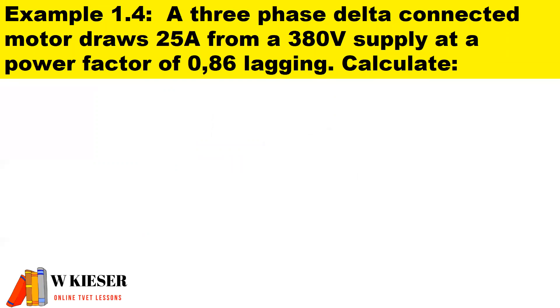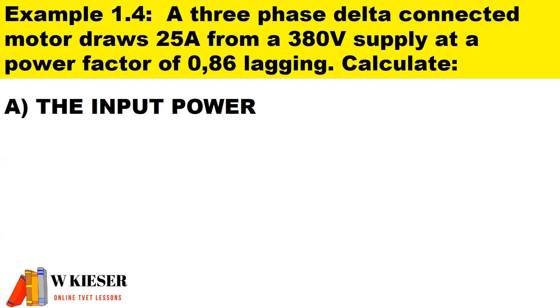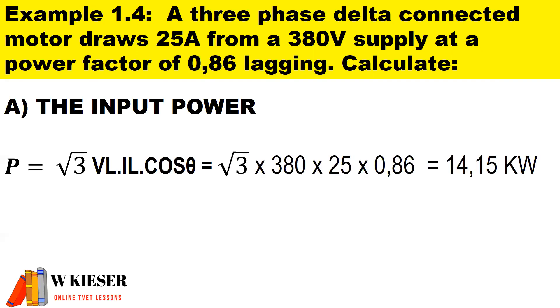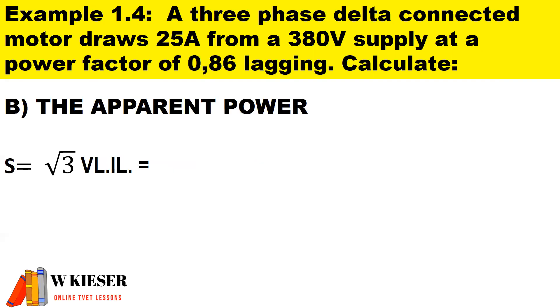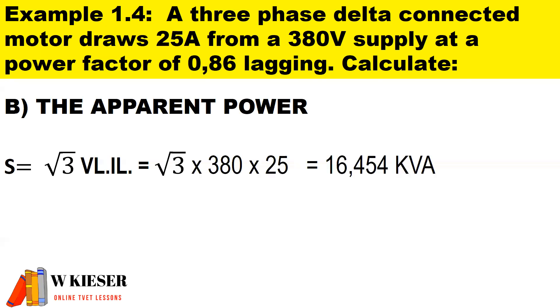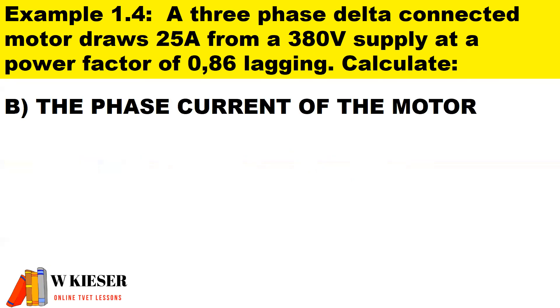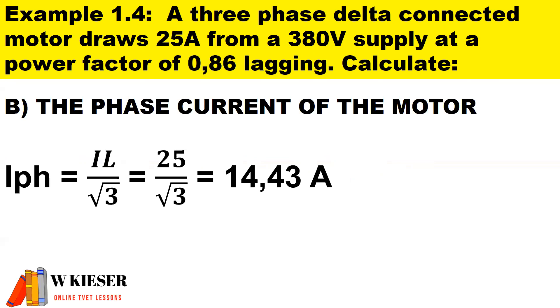Example 1.4: a three-phase delta connected motor draws 25 amps from a 380 volt supply at a power factor of 0.86 lagging. To determine input power, multiply by square root 3 (three-phase circuit): √3 × 380 × 25 × 0.86 = 14.15 kilowatts. The apparent power (S) is √3 × 380 × 25 = 16.454 kilovolt-amps. For a delta connected motor, the phase current is IL divided by √3: 25 ÷ √3 = 14.43 amps.